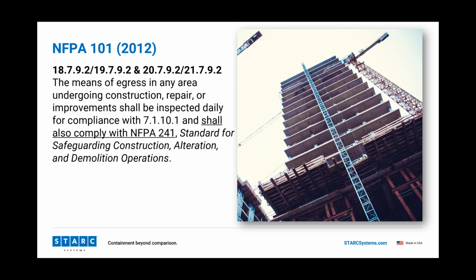So chapters 18 and 19, 18 is our new healthcare occupancy chapter, 19 is existing, 20 is new ambulatory, and 21 is existing ambulatory. All four of these chapters point us directly to compliance with NFPA 241. It's one line in the code that is often missed, but it is a shall requirement. So let's dig into really what that looks like.